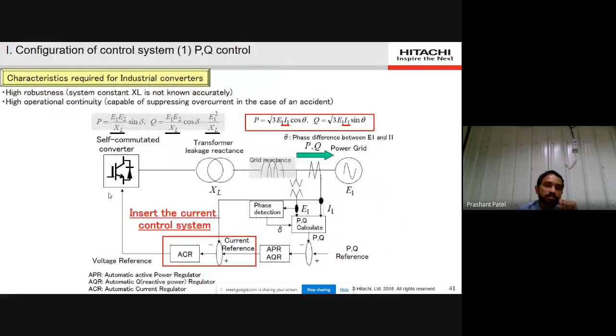The error feeds to this APR, which means active power regulator, and there are two separate loops. One is the APR loop, another is the AQR loop. It generates the current reference. That current reference is compared with the actual current. It generates an error and gives it to the inner current loop, and it generates a final modulating waveform. It feeds to our converter. So that is one control strategy, based on real and reactive power.